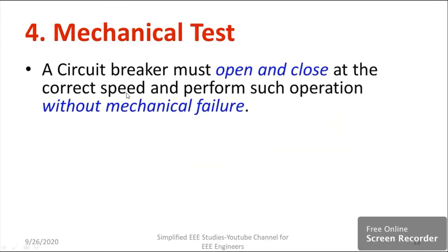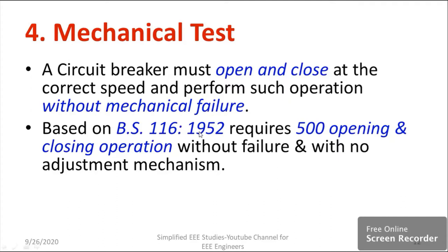I would like to explain about the mechanical test. The circuit breaker must open and close at the correct speed and perform such operation without any mechanical damage. So that's the main agenda for conducting the mechanical test. The operation should be very comfortable, and no mechanical failure should occur. It is mainly based on the BS116-1952 standard. According to this specification, 500 openings and closings should be done without any failure. If you take a new test circuit breaker from the industry outlet, it has to perform 500 openings and closings without any failure.